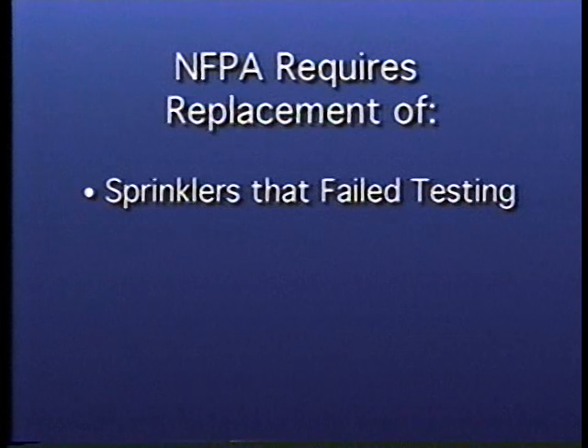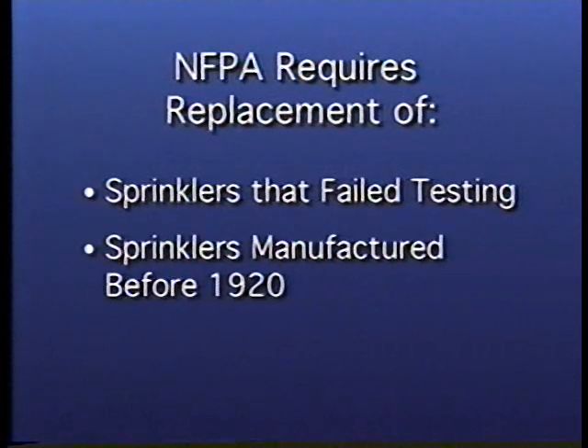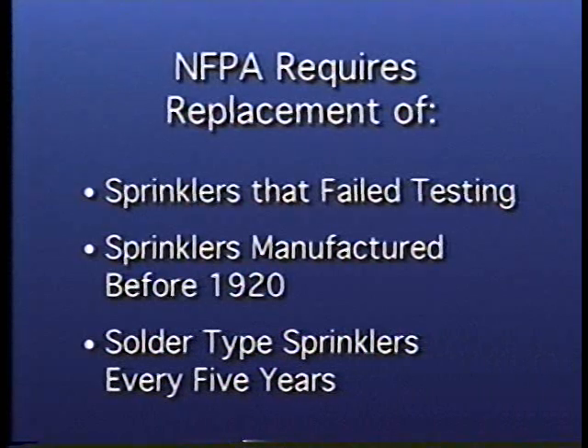NFPA 25 also requires that any sprinklers manufactured prior to 1920 should be replaced. In addition, NFPA 25 stipulates that extra high-degree solder-type sprinklers, which are exposed continuously or nearly continuously to the maximum allowed temperature of 300 degrees Fahrenheit, are to be replaced at 5-year intervals. This is due to the solder migrating into the link to form a new alloy having an extremely high melting point, thereby effectively preventing a sprinkler from operating.